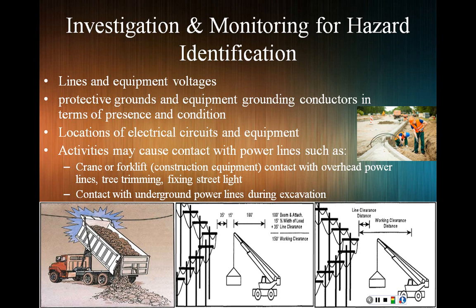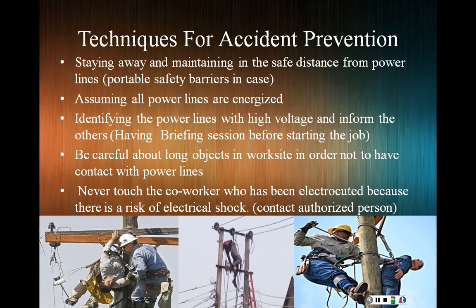The clearance working distance for the crane is 150 feet, and the line clearance distance is just 35 feet, based on the pictures. Techniques for accident prevention: staying away and maintaining a safe distance is the most important thing. Sometimes, especially for workers who work with power lines, we use portable safety barriers for other workers at the work site. We should assume all power lines are energized, identify the high voltage power lines, and tell others about that by having pre-job briefing sessions.